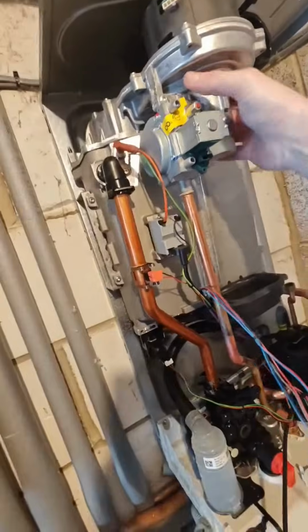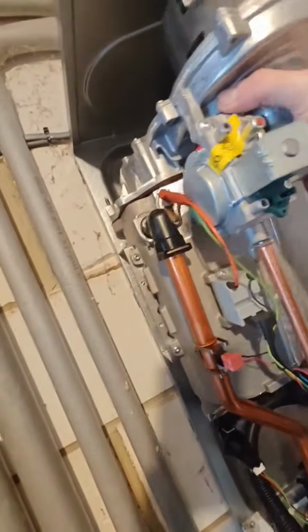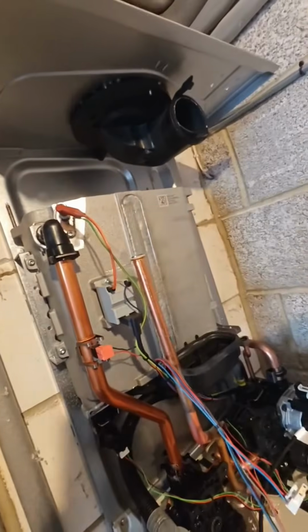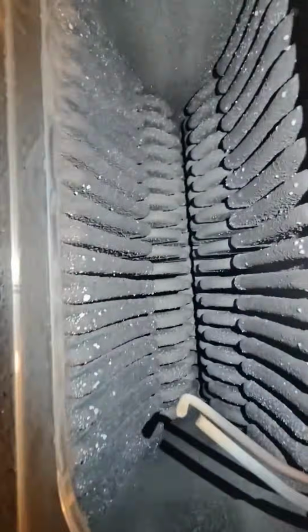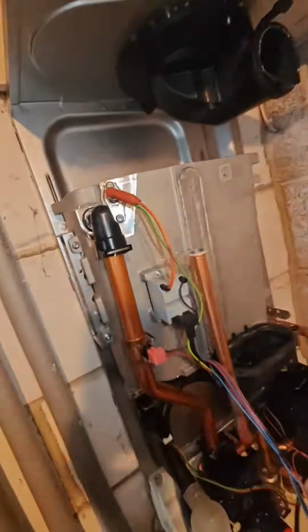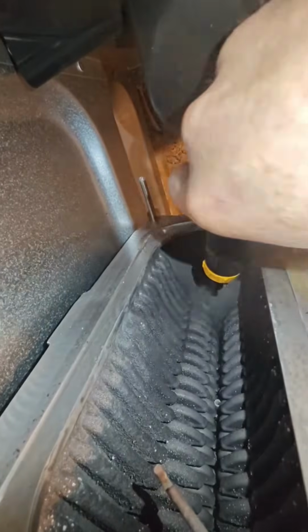So more parts to come out the boiler. I'm removing the gas valve, the fan and the burner. So we can get into the heart of the boiler, which is the main part of the 5-year service. Once we've removed the burner, we can get into the main heat exchanger, which is the heart of the boiler, and we can give this a good clean with the jet wash.